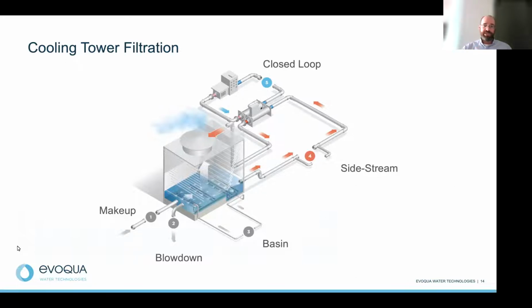But here are just some typical spots you might see that maybe you need to put something on the makeup water. I've had folks before pull from a river that's very dirty. And so that makeup water is very dirty and they want to get that cleaned up before they introduce that into the tower. Bullet point number 3 there, the basin. If you looked in your basin before and you got a lot of sediment built up, maybe that's a great spot to do some filtration, some basin agitation. Number 4, the side stream filter there. That's a great place to put a side stream filter because you're going to get that water cleaned up before you send it back to your heat exchanger and your cooling tower.